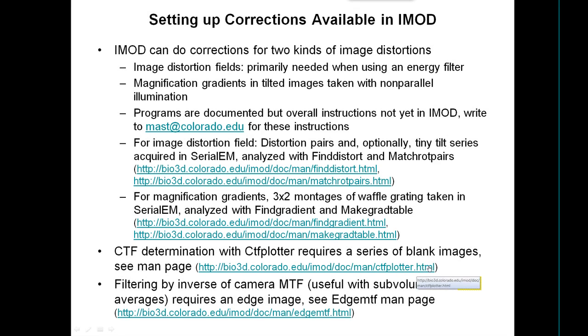CTF determination using Ctfplotter requires a series of blank images, with the procedure fully described in the manual. For MTF correction, which corrects for attenuation of high frequencies by the CCD camera, you filter by the inverse of the MTF — this is really useful with sub-volume averages where data are clean but high-resolution detail has been attenuated. You measure the MTF from an edge image taken in the microscope and analyze it with the program edge_MTF.